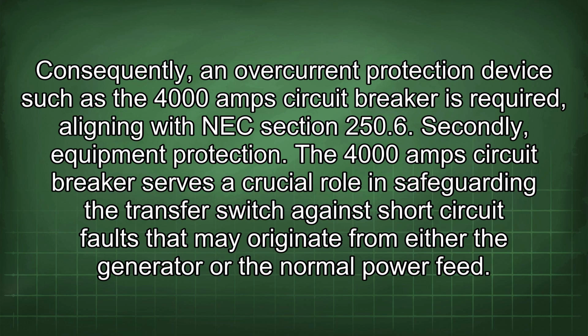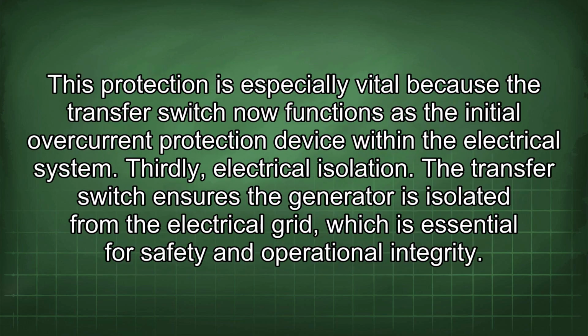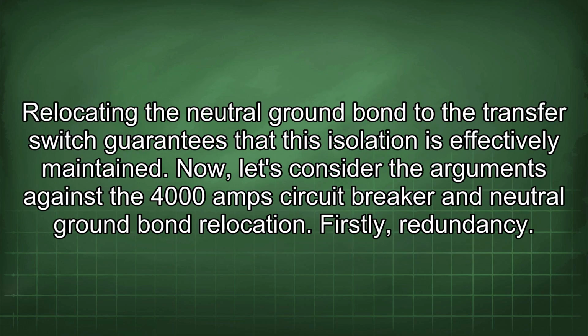Secondly, equipment protection. The 4000 amp circuit breaker serves a crucial role in safeguarding the transfer switch against short-circuit faults that may originate from either the generator or the normal power feed. This protection is especially vital because the transfer switch now functions as the initial overcurrent protection device within the electrical system. Thirdly, electrical isolation. The transfer switch ensures the generator is isolated from the electrical grid, which is essential for safety and operational integrity. Relocating the neutral ground bond to the transfer switch guarantees that this isolation is effectively maintained.